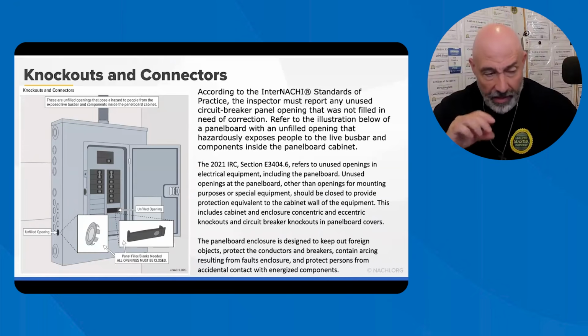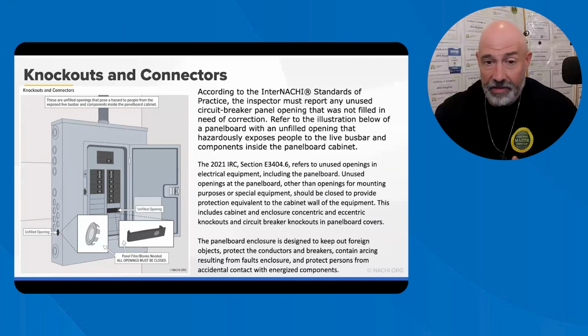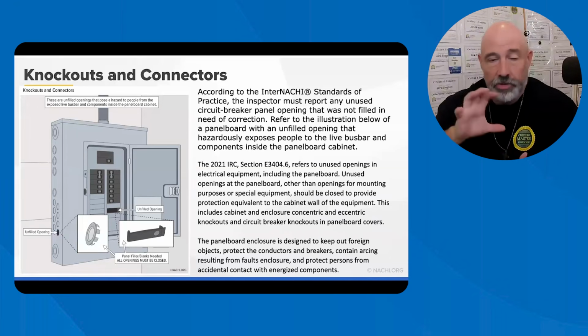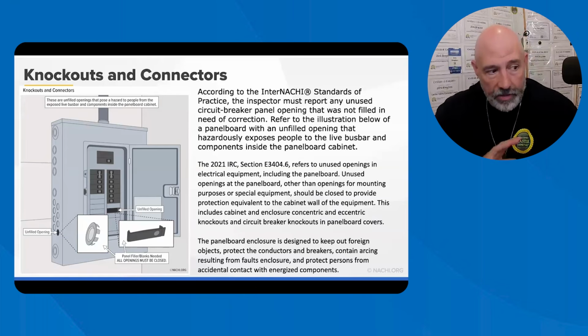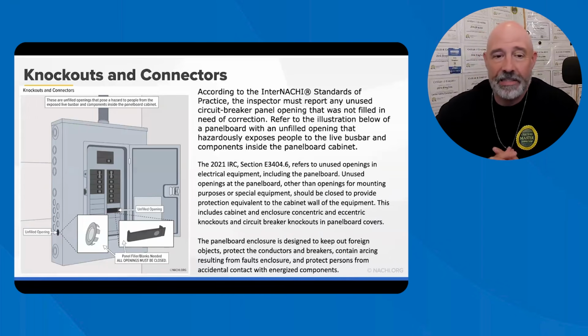But when you don't have that cover over the slot where the circuit breaker is, that's a no-no, because somebody could stick their finger in there, and I'm sorry, you're going to be having a funeral if they do that. So you don't want that. So cover all those openings. Make sure that they're covered. Make sure that you put them in your report. And, if anything, further evaluation from an electrician if you're not sure.